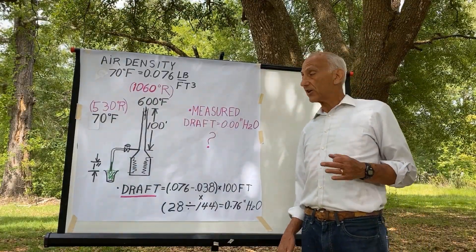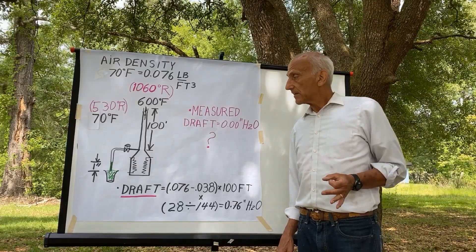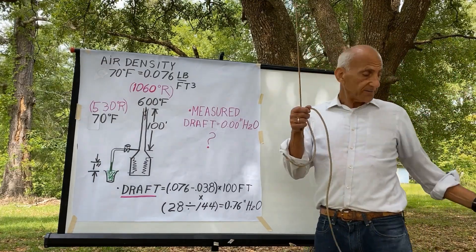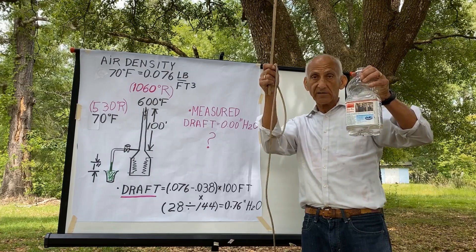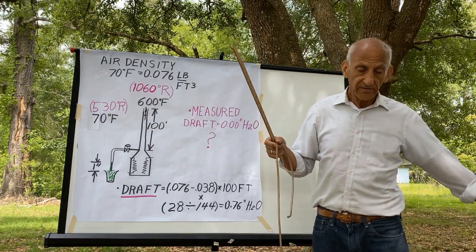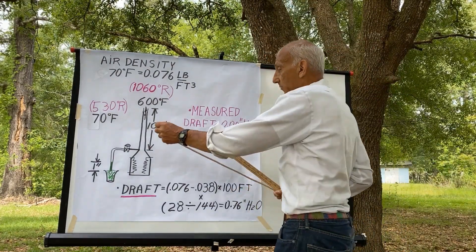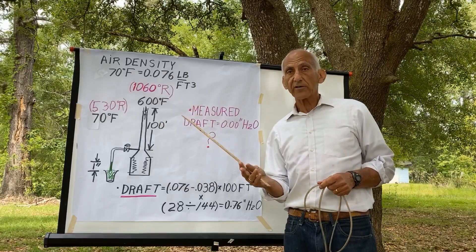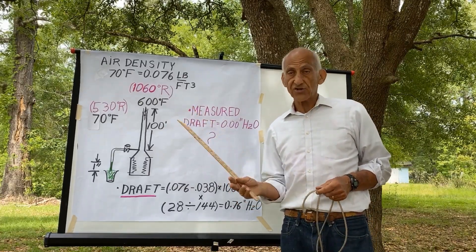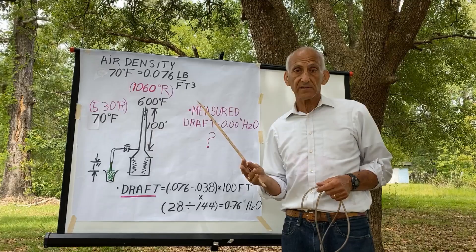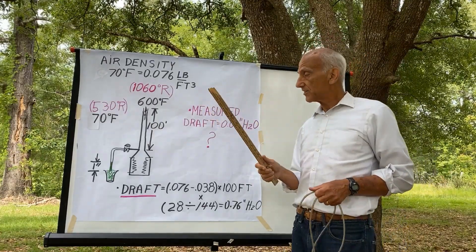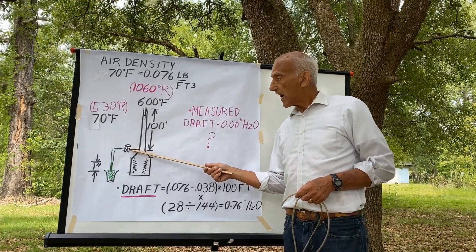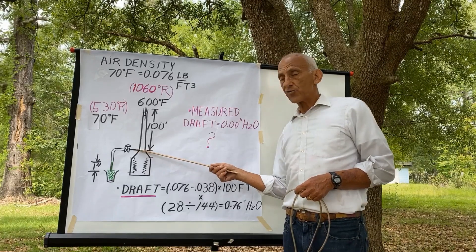So what I decided to do is to go out and measure the draft myself. To measure draft, I typically just take a bottle of water and a piece of plastic tubing, insert the tubing at some point where I want to check the draft, and see how far the water is drawn up into the tubing. The level of water that is sucked up is inches of water draft. And just as they suggested, when I go out and measure the draft below the bottom row of convective tubes, I measure a draft of zero.